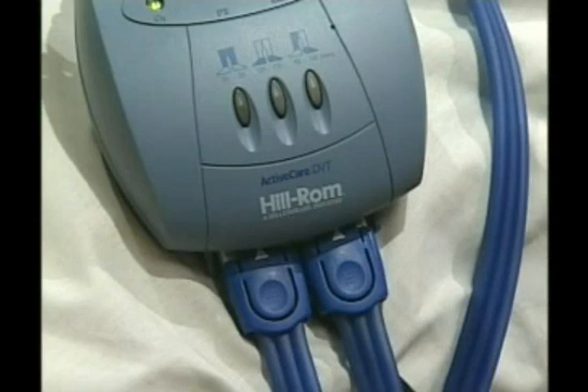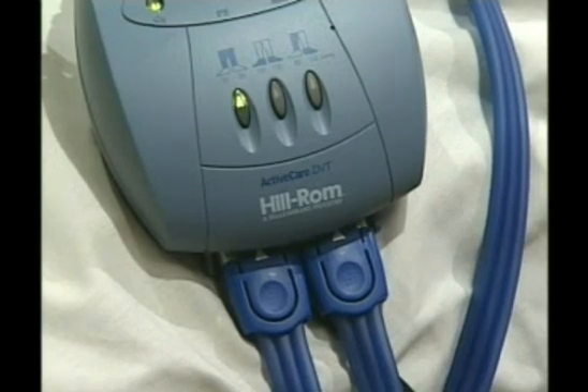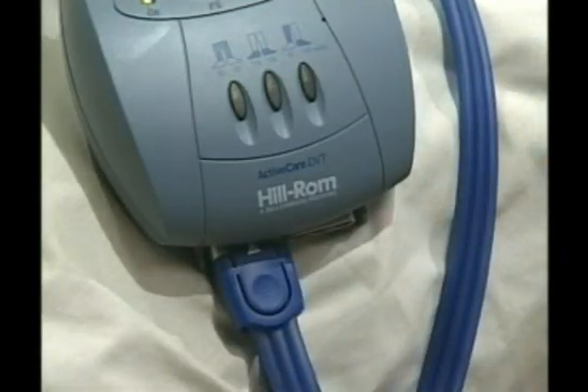Following the self-test mode, the ActiveCare DVT unit will automatically identify the specific sleeves that are being used and select the correct mode of operation. This may take up to 2 minutes. The operation mode light will illuminate below the appropriate program icon. If only one sleeve is used, this light will blink.